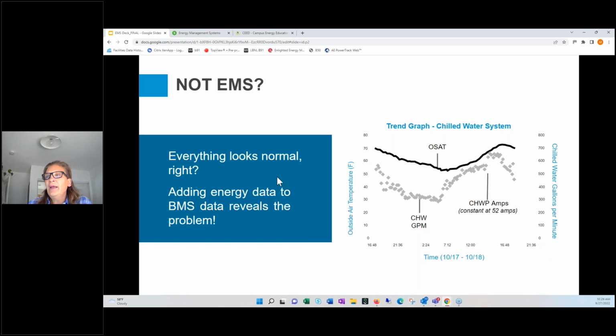Okay, and another example is for an EMS, actually, let me say, this is typical of a BMS. As a commissioning agent, what we're looking at here is a chilled water system, and we have some data that's being trended over time. The top line is outside air temperature, and the bottom line is our chilled water gallons per minute, so how much we're flowing of our chilled water. And if I was a commissioning agent and I wanted to say, hey, is this system performing properly? I would look at this data and I would say, yeah, it looks good to me.